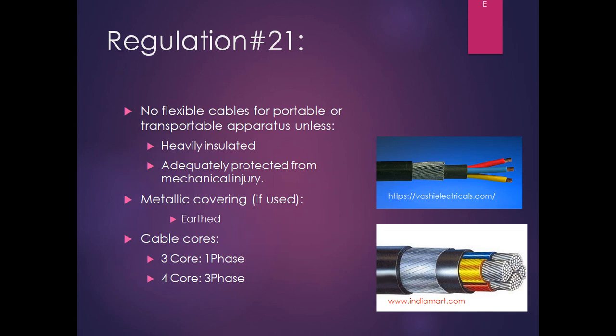Regulation 21 says that no flexible cables should be used for portable or transportable apparatus unless they are heavily insulated and adequately protected from mechanical injury. If you see the industrial accident rates, a huge number of accidents occur from the portable equipment or transportable equipment like welding machine, cutter, grinder, etc., which can be easily moved. Many a times the cutting wheel damages the supply cable and that may lead to the fatal accident.